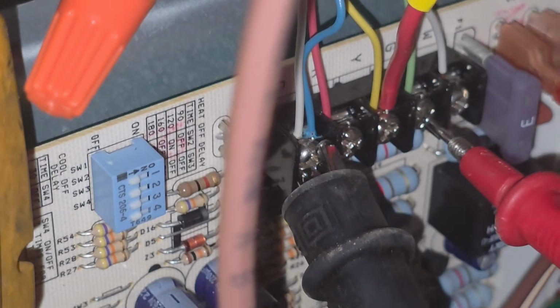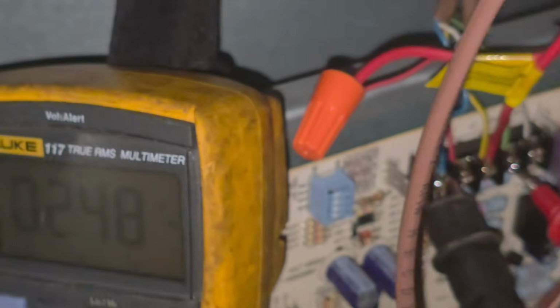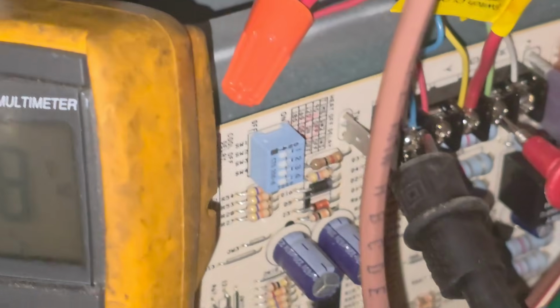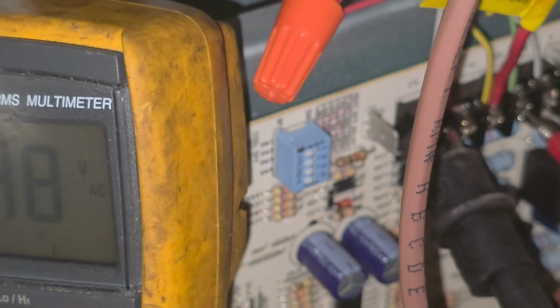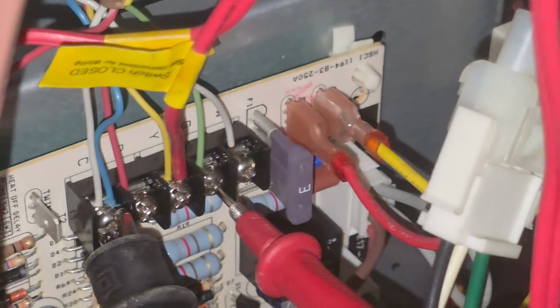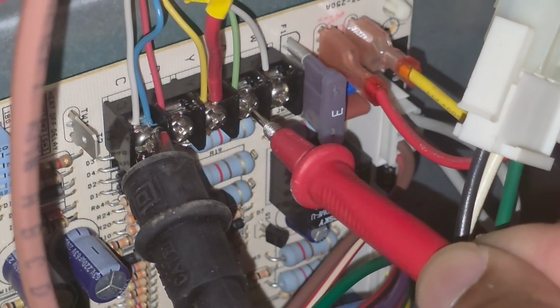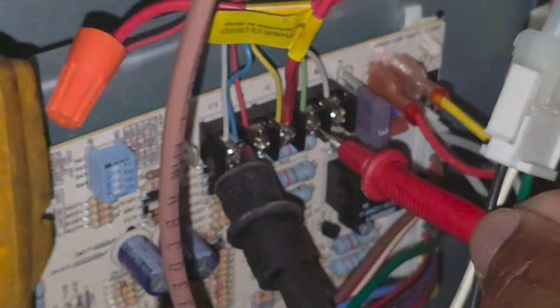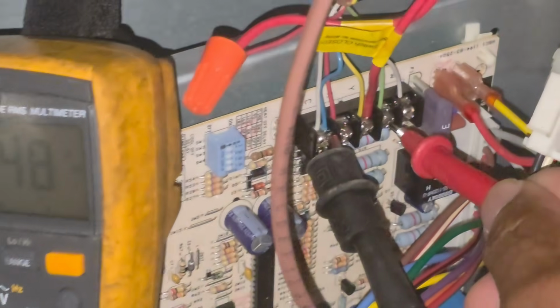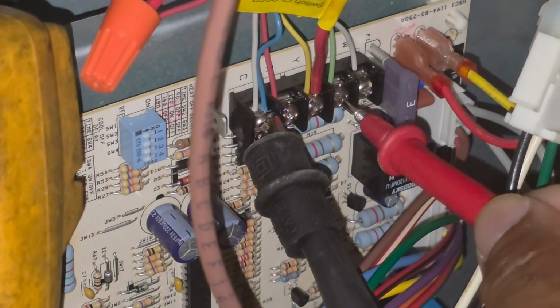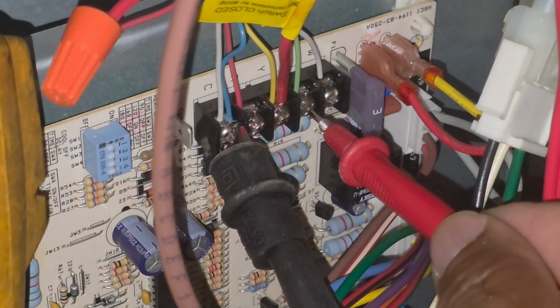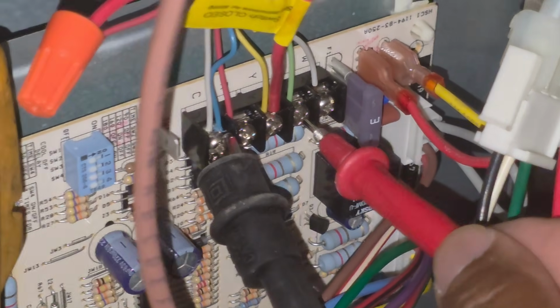Let's go to the fan. Now, you can see my fan is on, right? My fan is on, but it's not calling for fan. If I was calling for fan only on my thermostat, that's when I would be getting 24 volts. I should get 0 right now because it's on the heat. The heat is calling the fan to turn on after the delay.